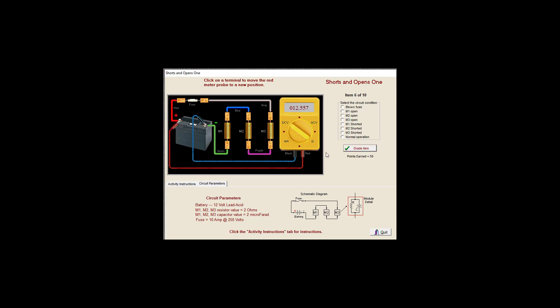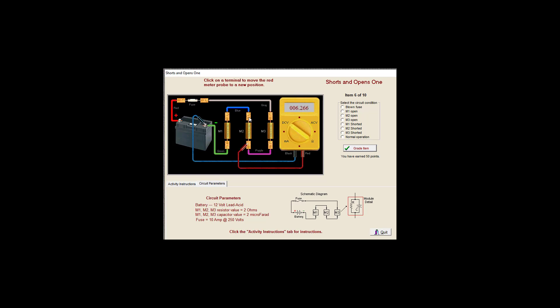Good. Good. Large voltage drop again, not good. Zero. Since this one's zero, I'm going to say that M1 is shorted to ground.